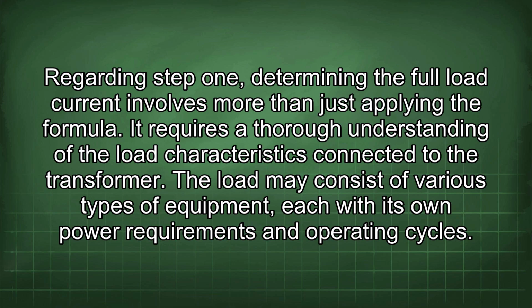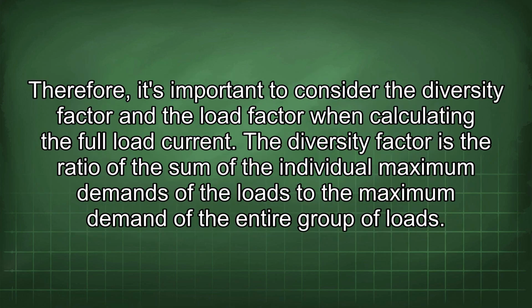It requires a thorough understanding of the load characteristics connected to the transformer. The load may consist of various types of equipment, each with its own power requirements and operating cycles. Therefore, it's important to consider the diversity factor and the load factor when calculating the full load current. The diversity factor is the ratio of the sum of the individual maximum demands of the loads to the maximum demand of the entire group of loads.